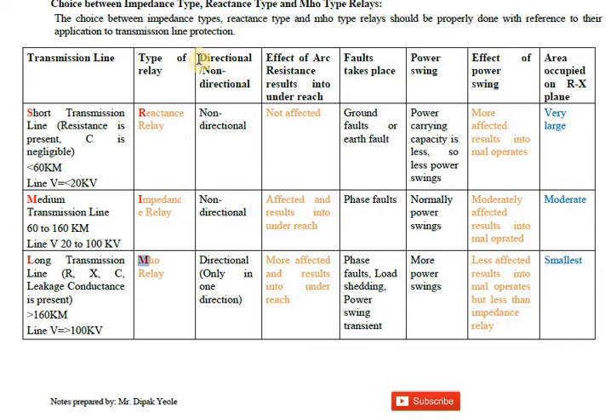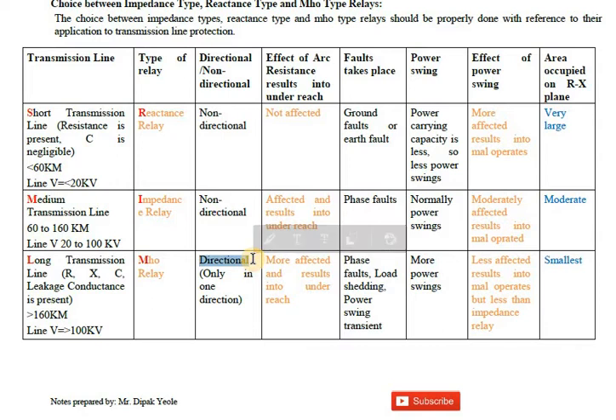The first parameter is the directional element. Reactance and impedance relays are non-directional relays, while only the Mho relay is directional — meaning it operates only when a fault occurs in one particular direction. If you haven't seen the directional relay concept, click on the icon for more information.